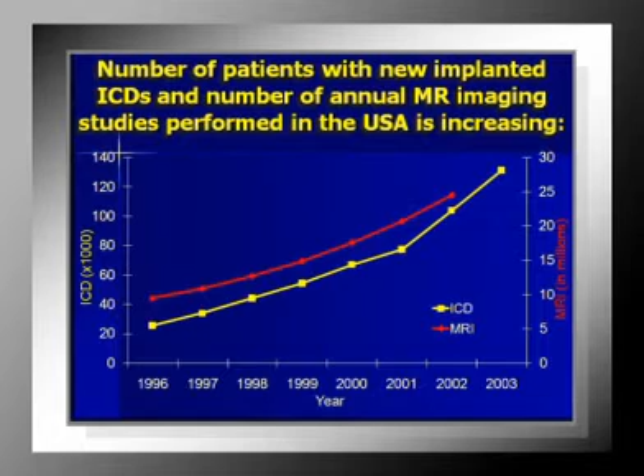So here's a graph showing the number of ICDs and MRIs over time. They're both going up dramatically. Early devices before 1990 were clearly not MRI safe. A number of studies showed that some were triggered by the gradient field, so these would have paced at 200 or 300 per minute. In this particular study at 0.5 Tesla, they were inhibited, pulsing at 800 per minute.